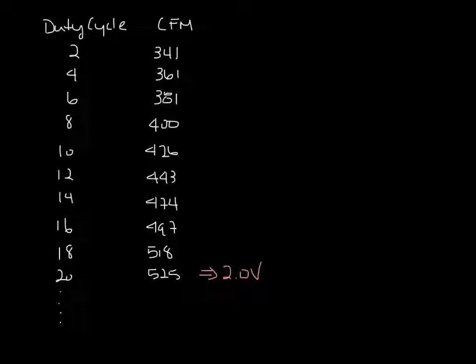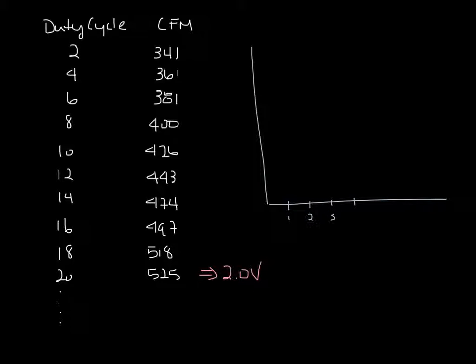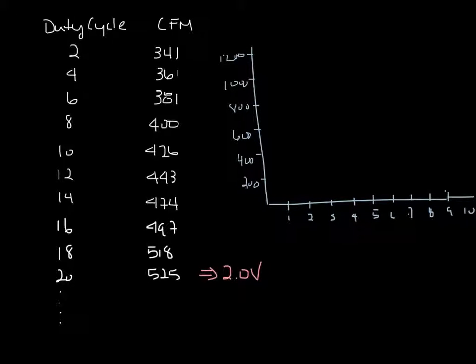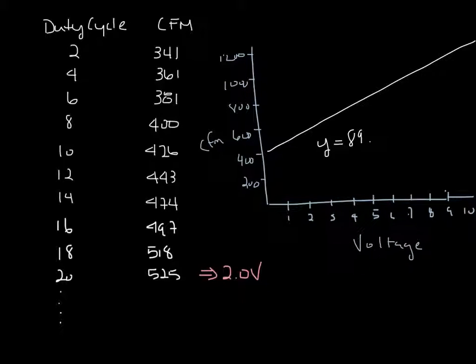So now I can take this duty cycle chart and plot it on a graph with voltage on the x-axis and CFM on the y-axis. And you'll see that it forms a line. Sometimes it's a straight line, sometimes it has a slight curve to it. Let's put voltage down here and CFM up here. The line can be described by an equation, say y equals 89.37 times x plus 360.35. This is actually the PWM calibration curve for our FLS low-profile fan box.